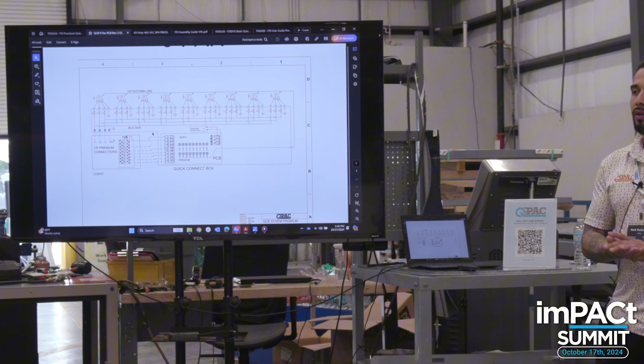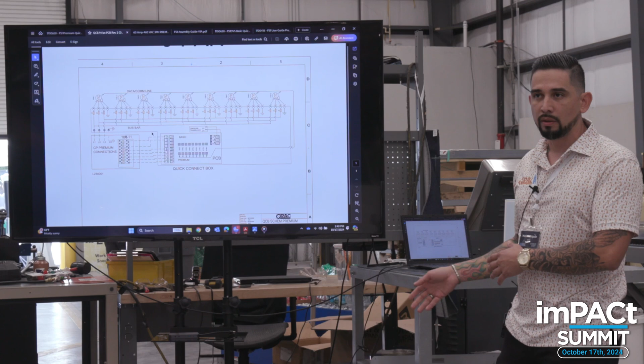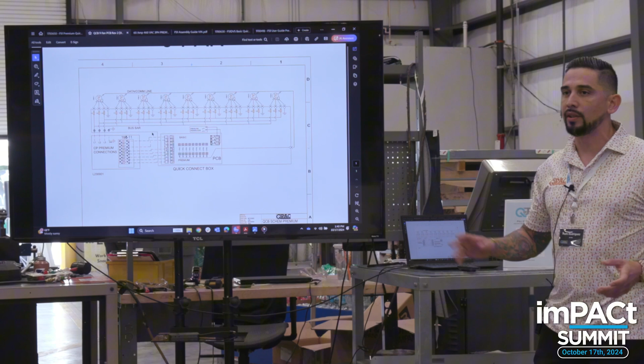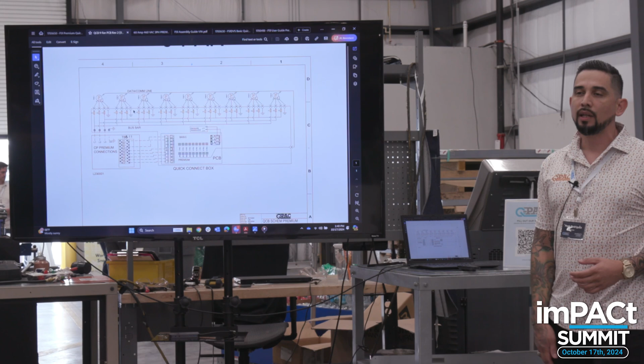That's in either hand or auto. They have to have it for either mode. So you need that for hand or auto, but you can run the unit still in hand without a start stop, which is just for auto mode. So this will work for hand as long as you have that safety made, you have power to the motors, and you can control it with the potentiometer. So that's just to get you running, get you airflow, because controls usually is not ready or you just want to get air moving.